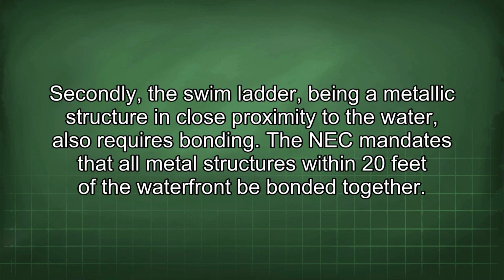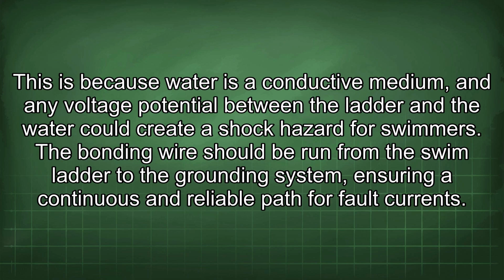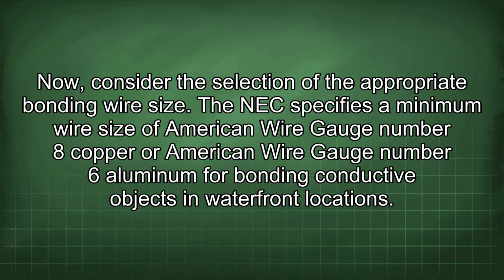Secondly, the swim ladder, being a metallic structure in close proximity to the water, also requires bonding. The NEC mandates that all metal structures within 20 feet of the waterfront be bonded together. This is because water is a conductive medium, and any voltage potential between the ladder and the water could create a shock hazard for swimmers. The bonding wire should be run from the swim ladder to the grounding system, ensuring a continuous and reliable path for fault currents. Now consider the selection of the appropriate bonding wire size.